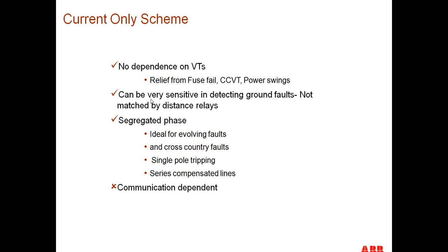We can make the relay very sensitive to detecting ground faults, much more secure than distance relays. It's very easy to do segregated phase, tripping each phase separately. So it's ideal for evolving faults or cross-country faults, for single pole tripping applications, or series compensated lines. And it is a communications dependent type of system.